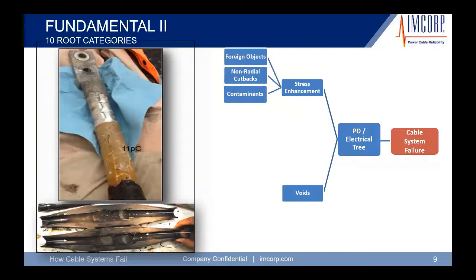Contamination. So when cables are made, it's made in a very clean room. You have the strand shield, your insulation, and your semicon material put over a piece of conductor in a very nice, neat, true triple extrusion, and there's really no contaminants. There's no issue in that area. When you try to do this in the field, in real life situations, you could be inside, on top of a cable tray, inside of a transformer, in a ditch. So these cables can get contaminated. If they get contaminated, that's an area for a void or a stress enhancement, and partial discharge can be activated. So eventually this cable would go to failure.